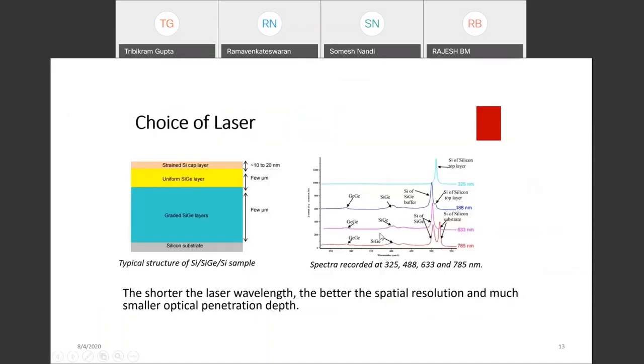What is the choice of laser? By using different wavelength lasers, we can get different information from the sample, such as different penetration depth. The laser source provides a stable and intense beam of radiation. Examples include: Argon ion giving 488 nm and 514 nm; Krypton ion giving 530.9 and 647.1 nm; Helium-neon laser giving 632.8 nm; near-infrared diode lasers giving 785 and 830 nm; and Nd:YAG laser giving 1064 nm. Short wavelength sources like Argon ion and Krypton ion lasers generate considerable fluorescence and cause photo-decomposition, so long wavelength sources like diode and Nd:YAG lasers can have higher power without decomposing the sample and also eliminate fluorescence.